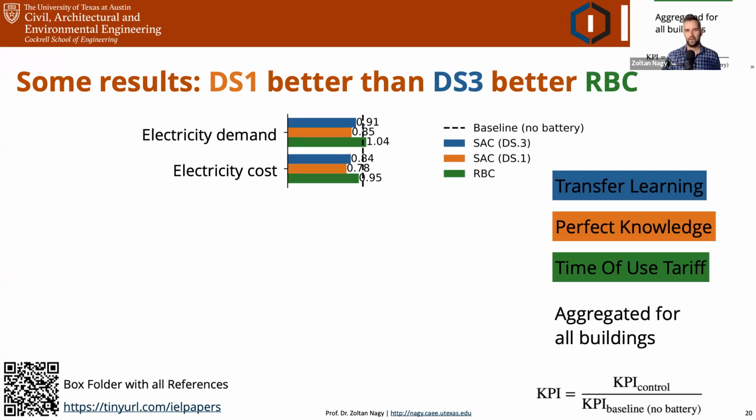The time of use tariff control for batteries does not give any advantage, and this is what a lot of the studies have found. And then they conclude that batteries have no advantage economically because there's very little that you can win. But the reality is that the controller is the problem, because with good control, you can pull out quite a bit more on the cost. So a few more KPIs that we looked at: emissions and costs are very related.